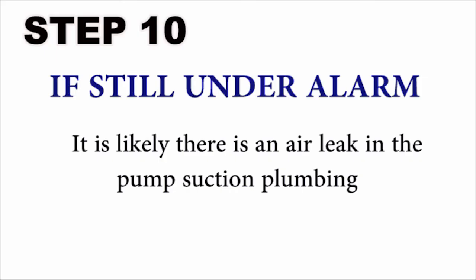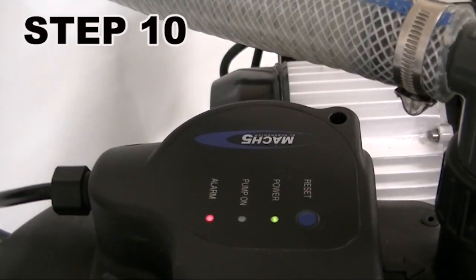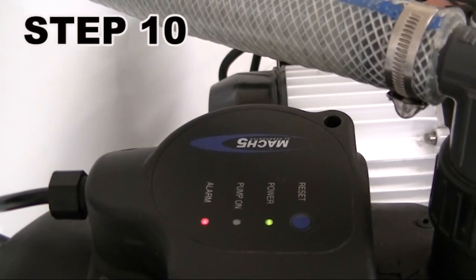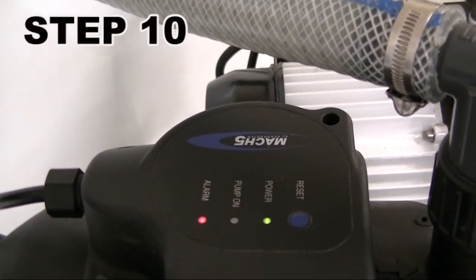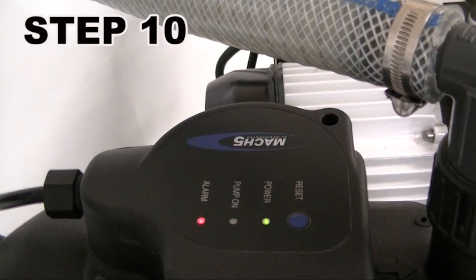If pump shuts off under alarm after performing the procedure, then air leaks in the pump's suction plumbing are likely. Please see suction leak identification video.